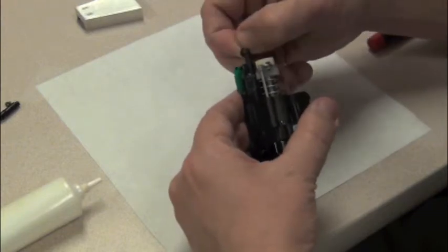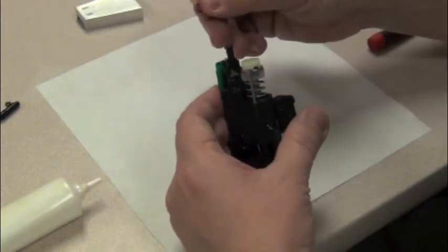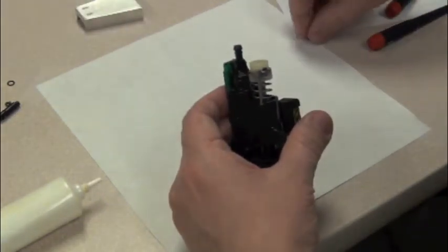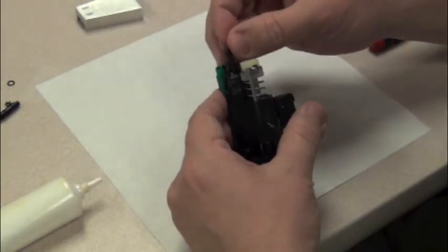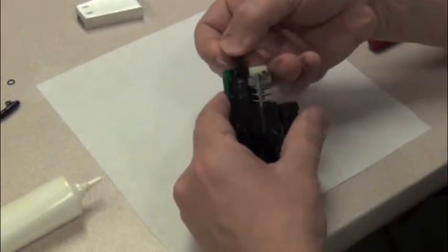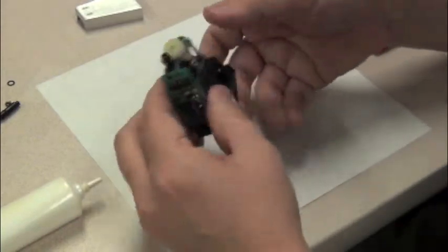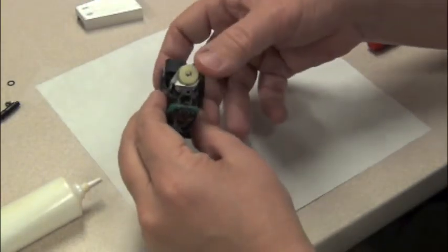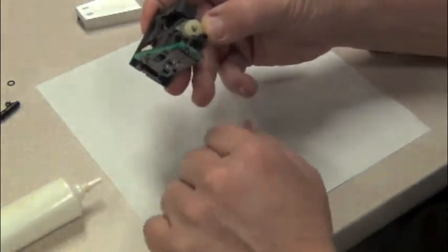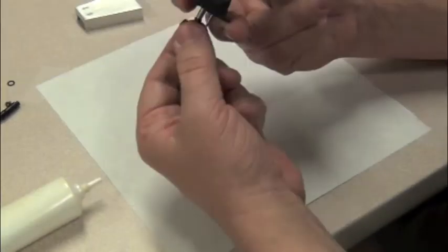Remove the O-ring on top of the spindle and throw that away. Grab the new O-ring and place it over the top. Grab a hold of the spindle from the screw side of the cap, hold it down, shake the spindle back and forth. Make sure that the spindle is free inside the housing.